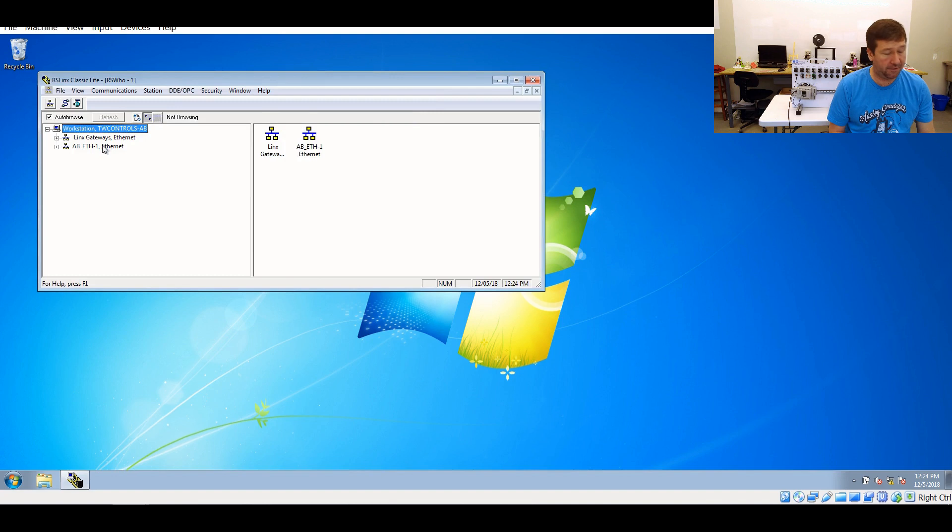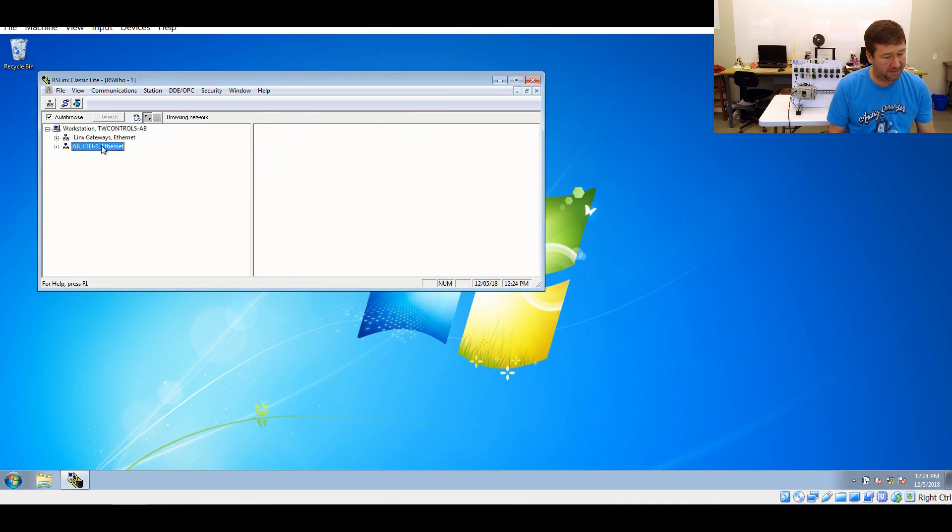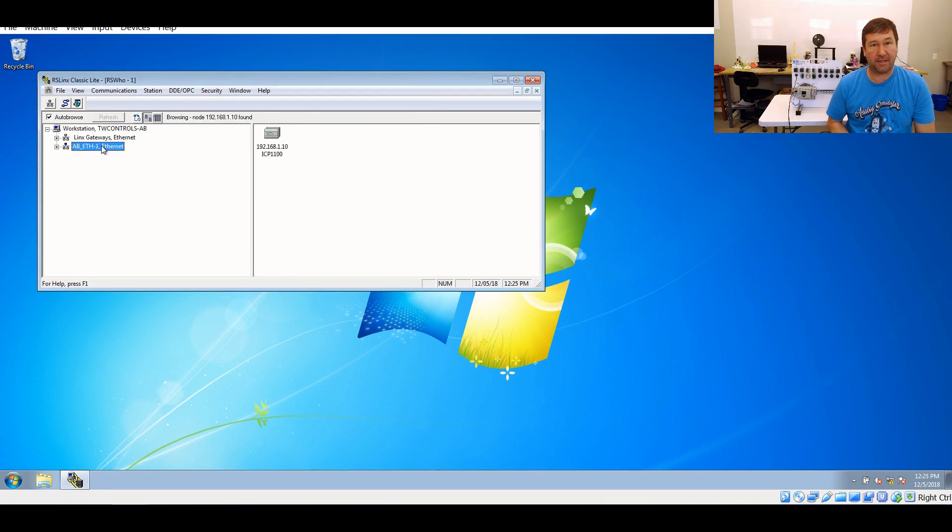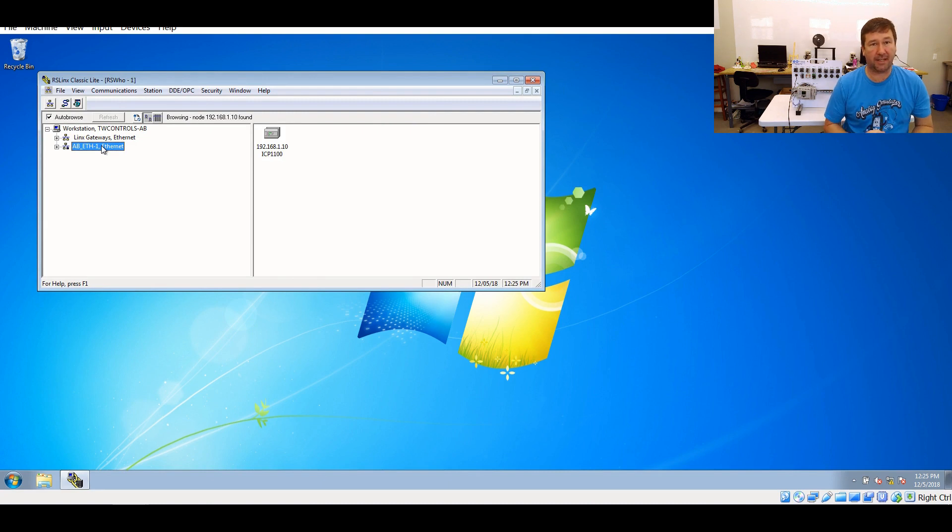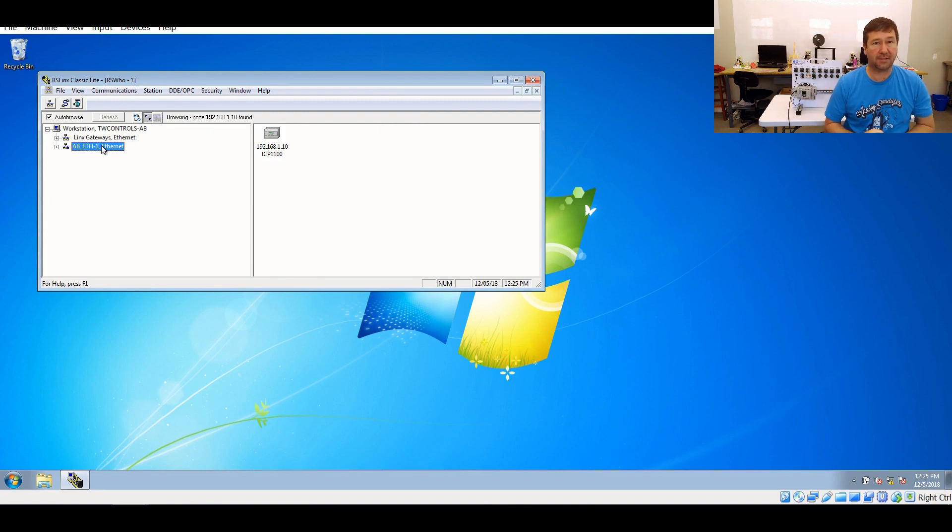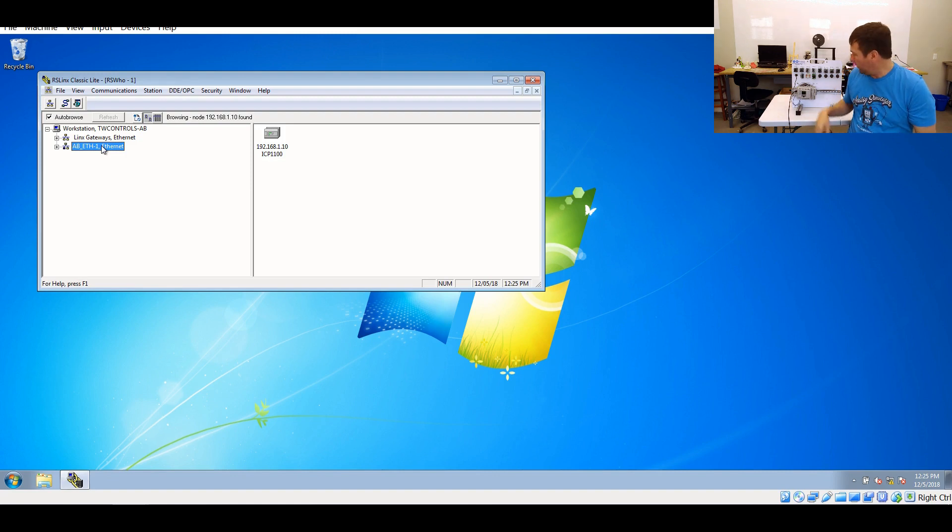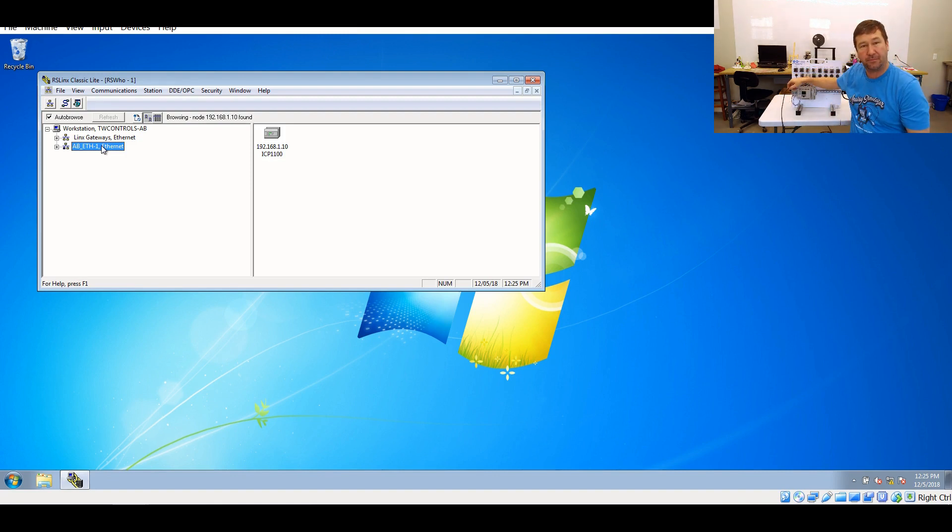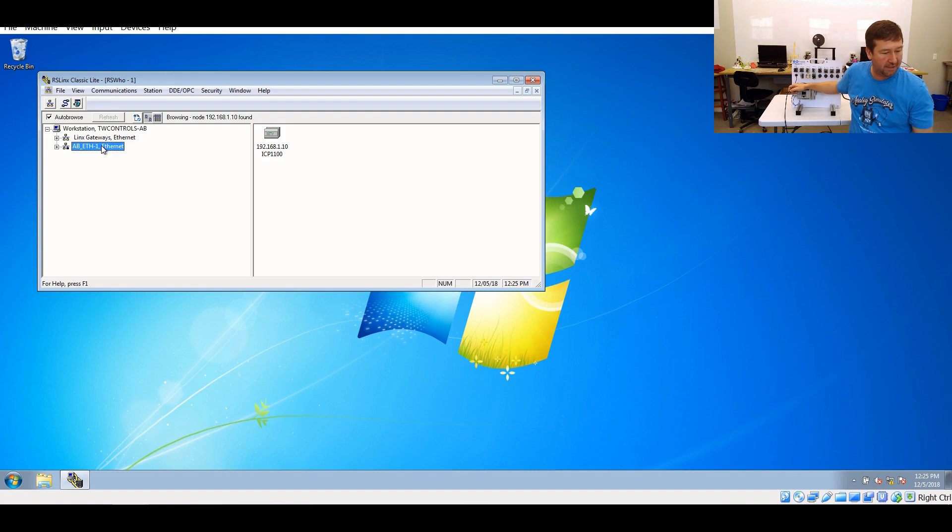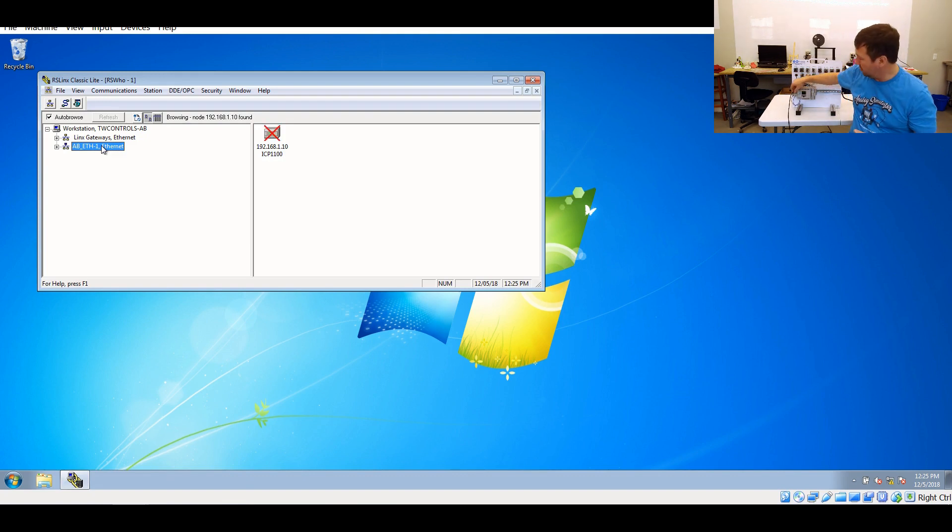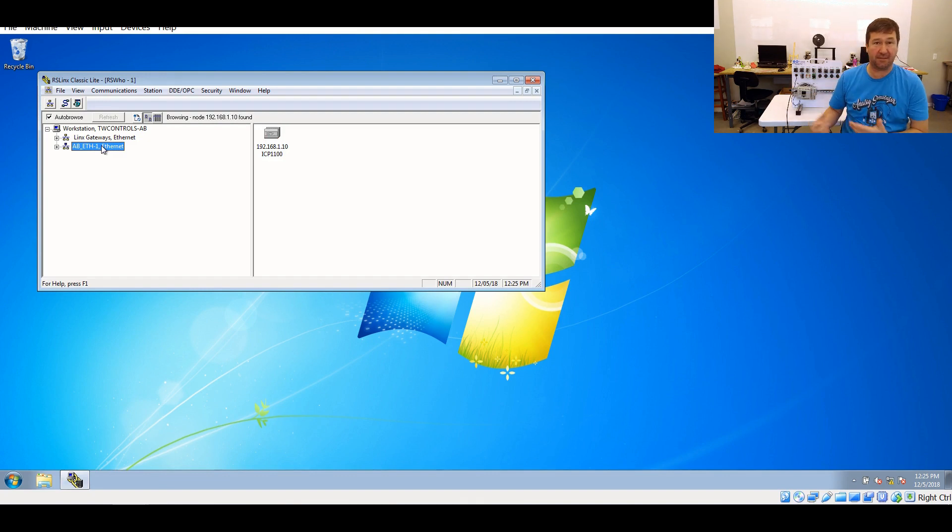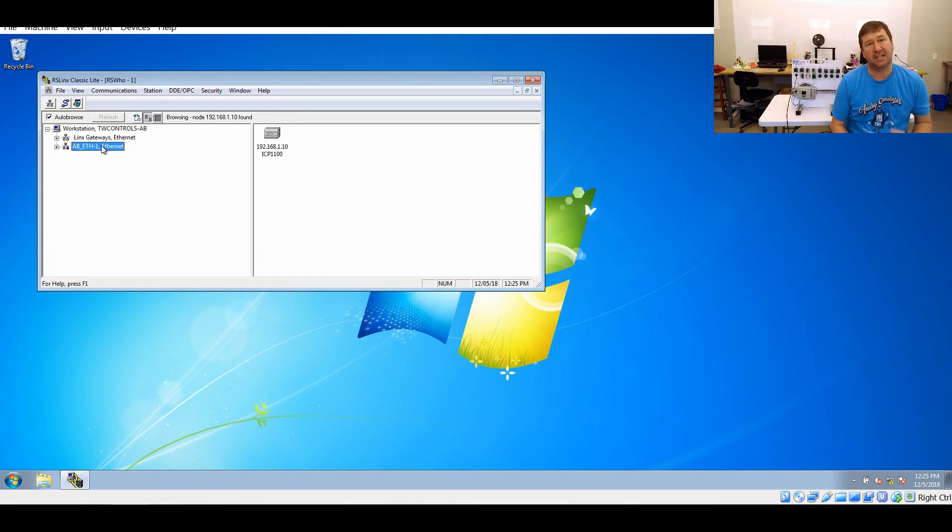Close. And now we're going to go to the Ethernet devices driver we just created. Now we can see that there's our PLC. So that's how you can go online through Ethernet IP or Ethernet devices. Again, it's always a good check if you're not sure what you're connected to, unplug the cable. In a few seconds, we should see a red X come up, which we do. We plug it back in. The red X goes away. So this is definitely the PLC that we're working with.